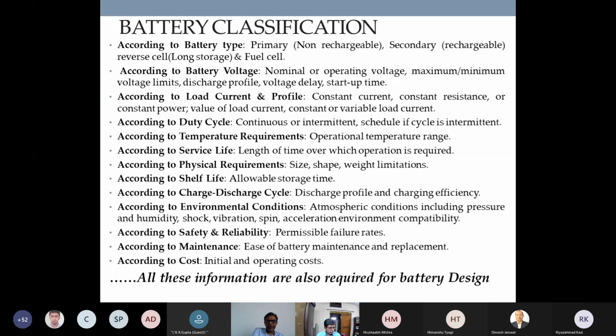Then the voltage delay - if the batteries are having a BMS, then things are a little different. Then the startup time, or we can say how much time the battery is supposed to deliver the current. Then the current and load profile - this is again very important, like what is the constant current, constant resistance, or constant power. According to the load profile, the batteries are being designed.